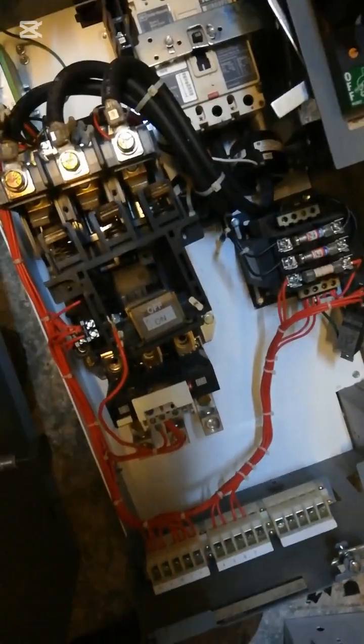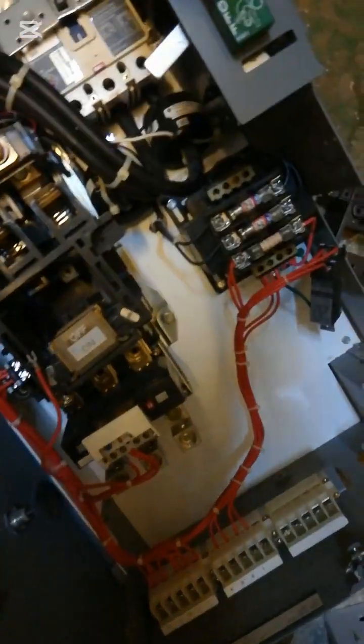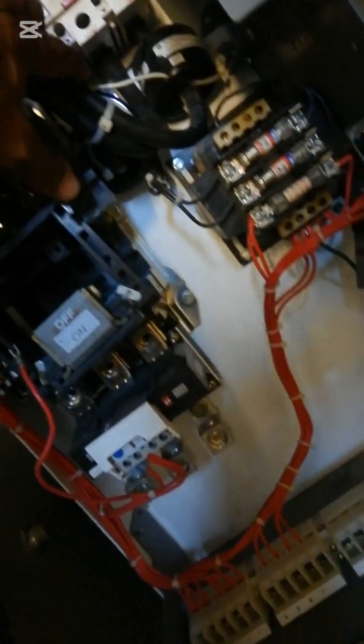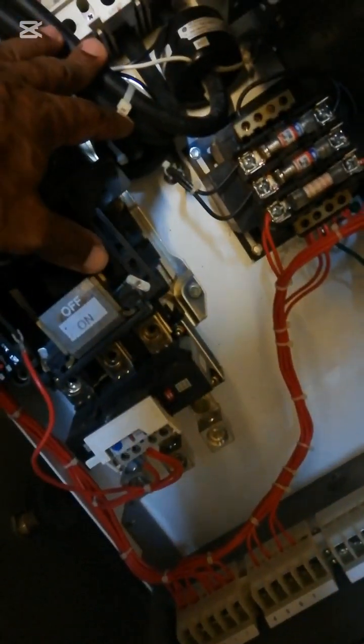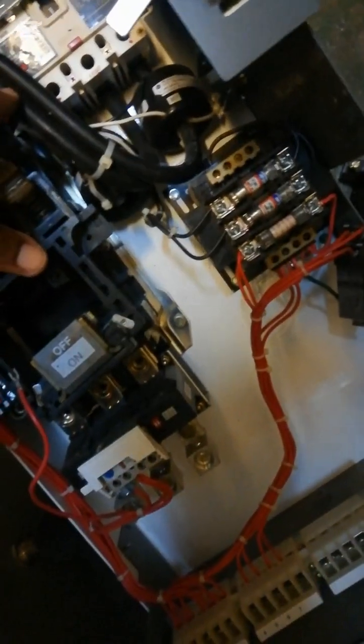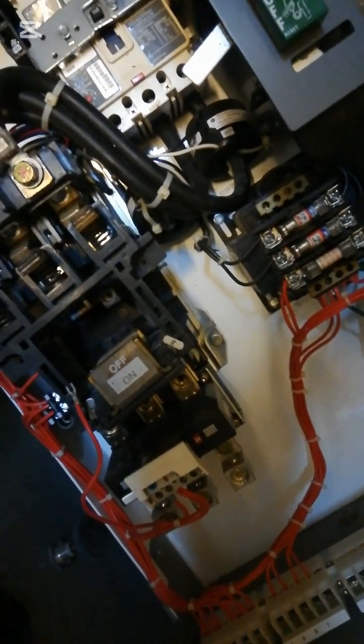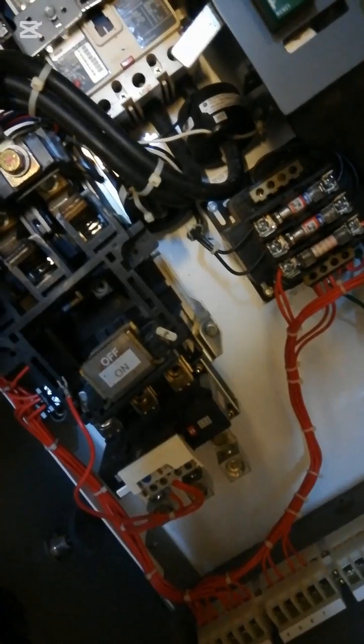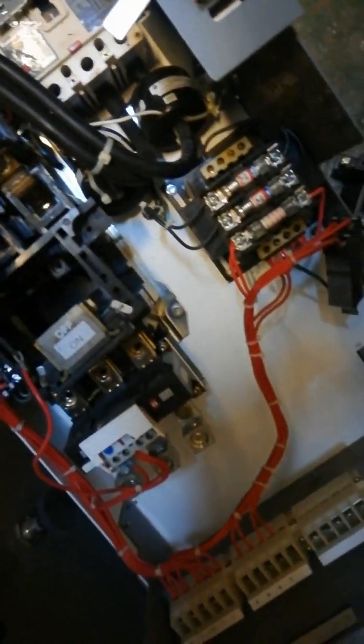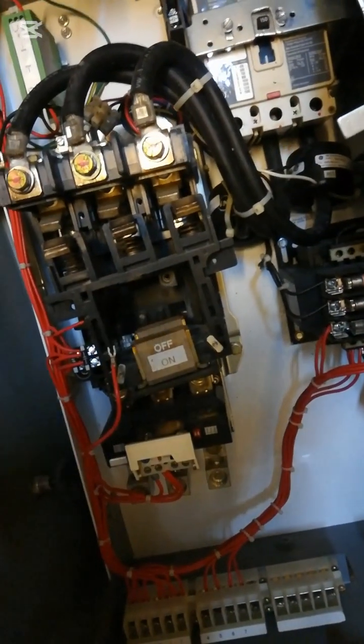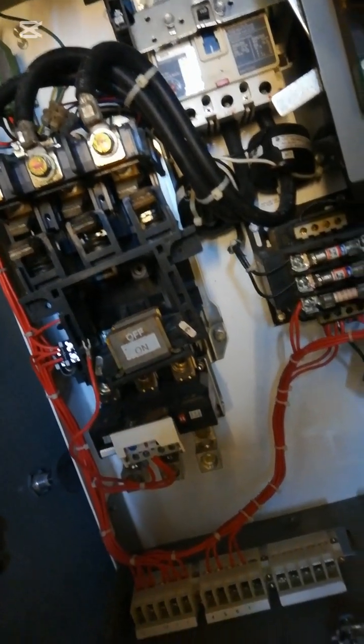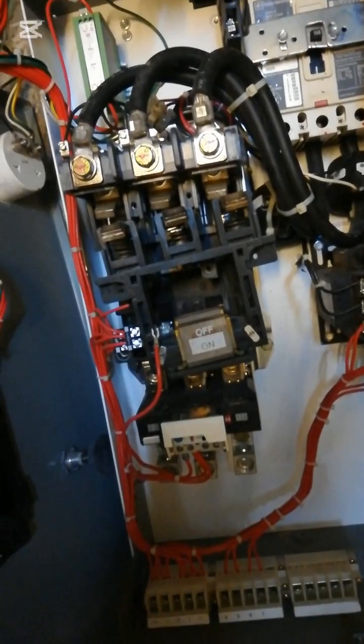Right? I did not tell you about these. These are called current transformers. These are connected to the same transmitter. So when it gets the magnetic field that goes around the cable here, it can now tell you the current that is going through each of the phases or the leads. I will tell you more as we go ahead, but for now, this is how the contactor looks when you pull it apart.